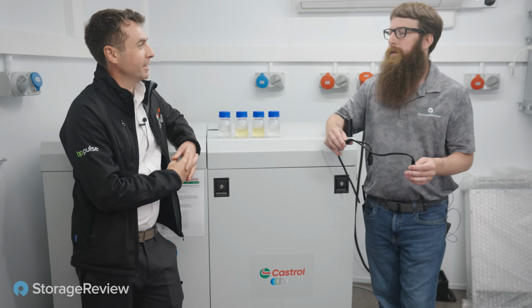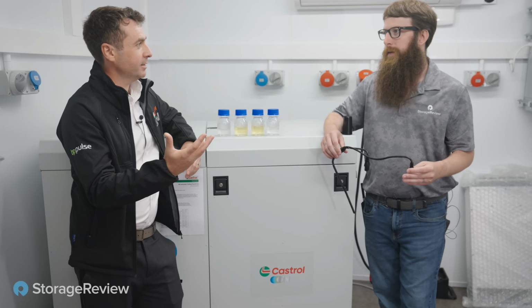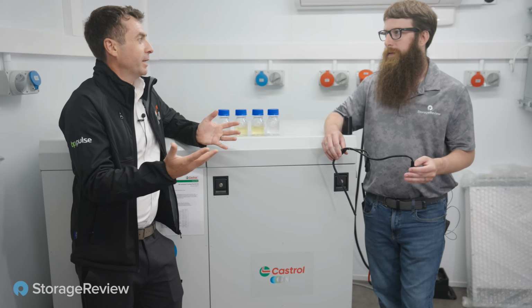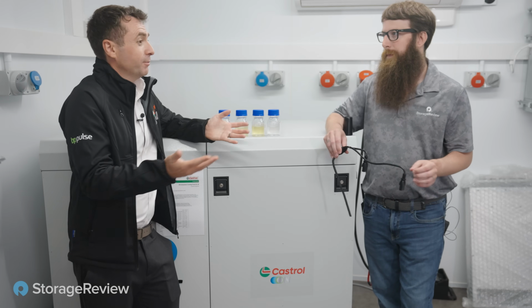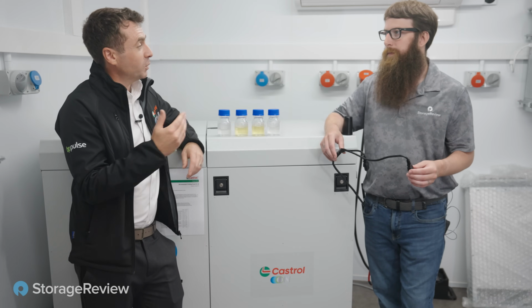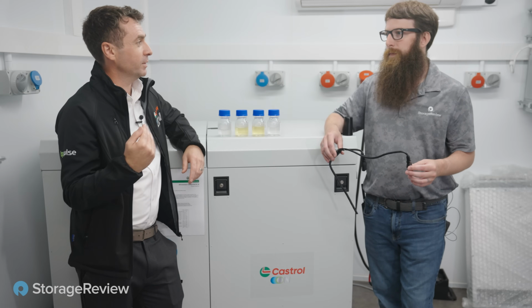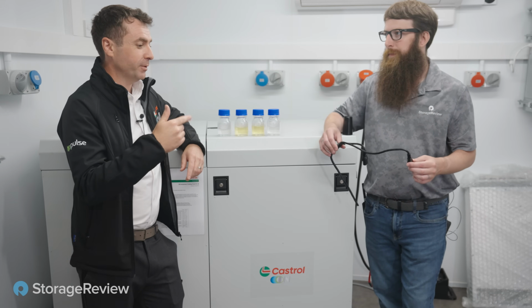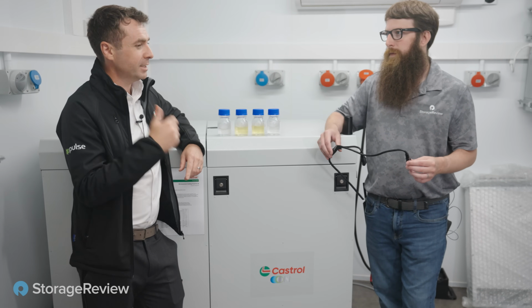You remove power energy from the server by removing the fans. If you imagine a server with a 2,400 watt power supply, for example, it could have 500 watts of fans - almost a 20% energy saving straight away by removing those fans. And the cooling efficiency that immersion cooling brings also means less pumping power.